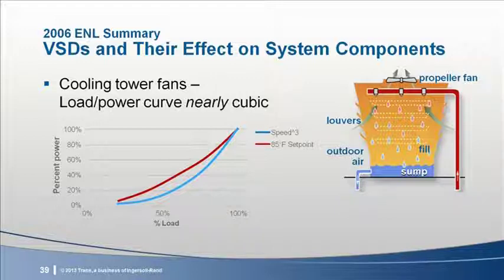This is because there are other things going on in the tower that influence its performance. Things such as water and airflow patterns and evaporation rates. Even so, a cooling tower is probably the component of a chilled water system which operates closest to the ideal cube of the speed power reduction with load.